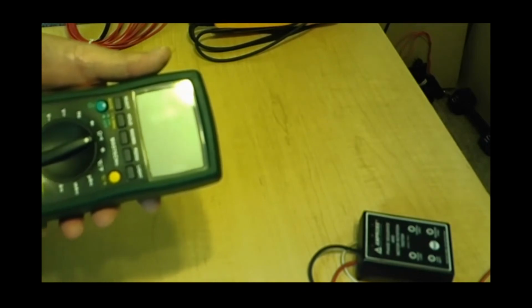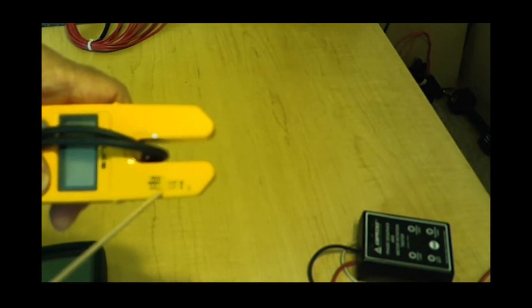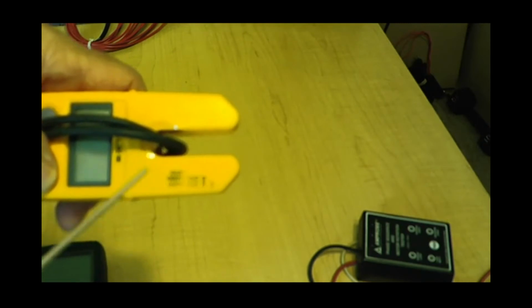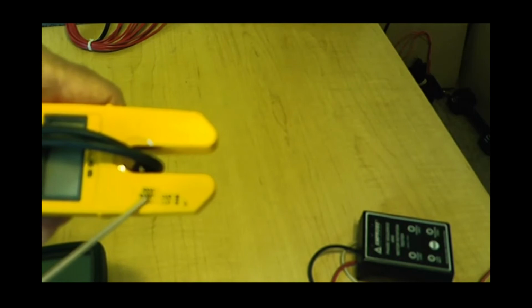Well, the category ratings are a rating where you can safely use the meter without seeing the meter explode. So this is what's called locations of use. There are 4 locations you can use. For example, a category 4 meter is used anywhere indoors, outdoors, anywhere that might have transient voltages. So it could be used in the building, out of the building, as long as it's 600 volts and less. If I go above 600 volts, this is only considered Cat 3. So in a facility, this Cat 4 meter could be used anywhere.